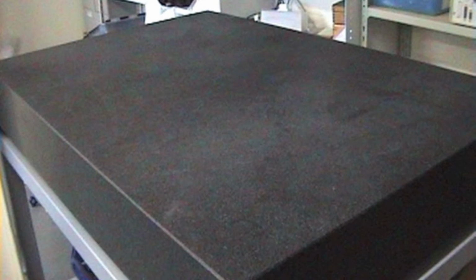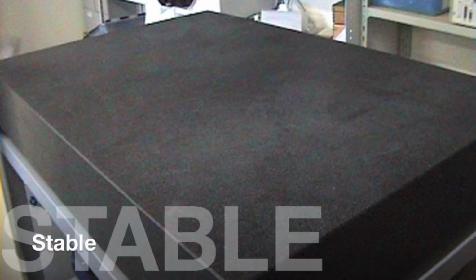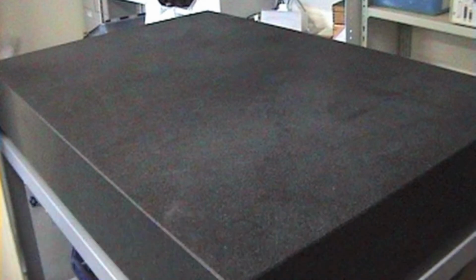Now some tips on the granite table itself. First of all, check that the table is stable. The best way to do this is to walk round the table and see if the Talyvel meter moves. Or put a weight on the table about the same size as a Talyvel and see if that changes the level itself.